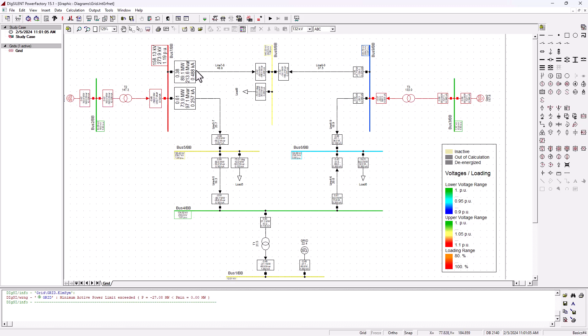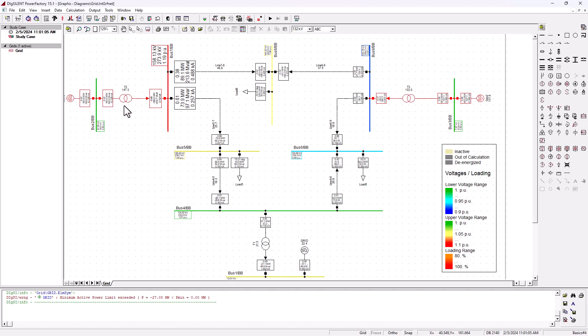A whopping 348 megawatt of reactive power that this generator is supplying. All of that is to compensate for the problems on the network. This is why power system networks basically charge consumers for reactive powers. If you're going to connect onto the power system network and you start distorting the power factor, then you're going to be charged for that because you're causing system instability.